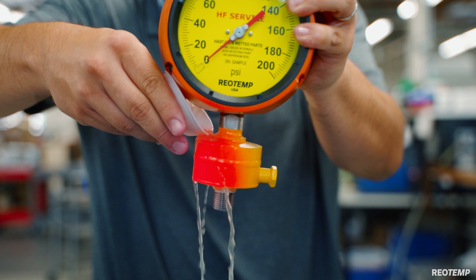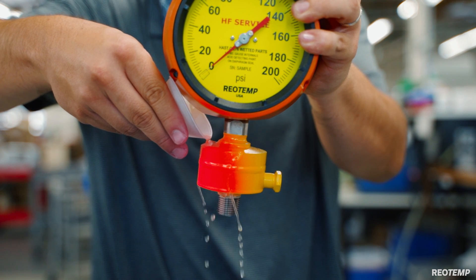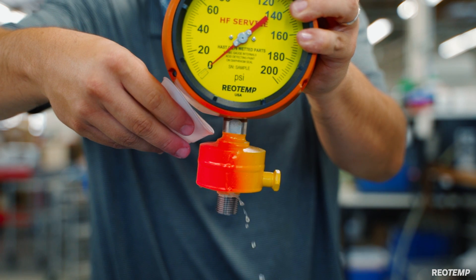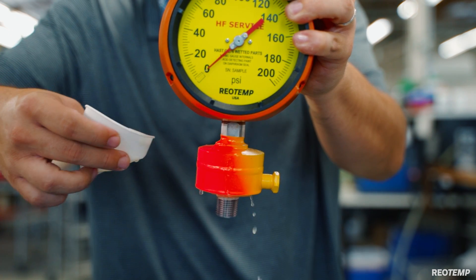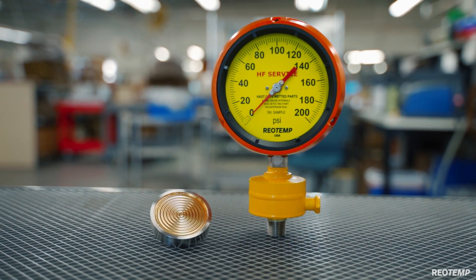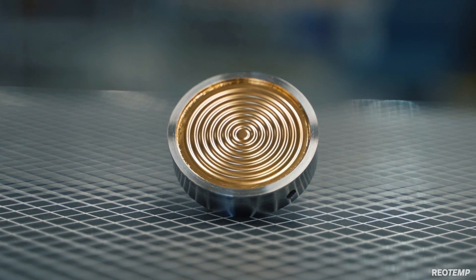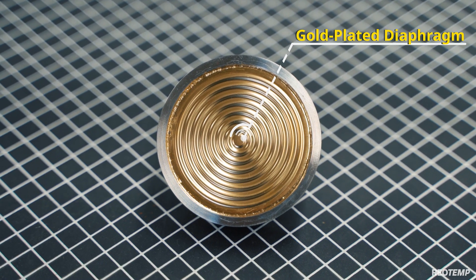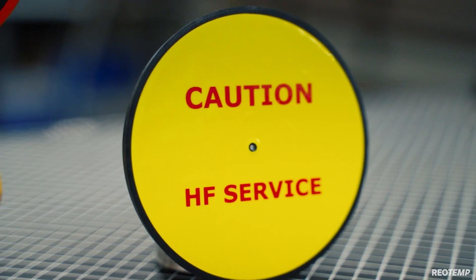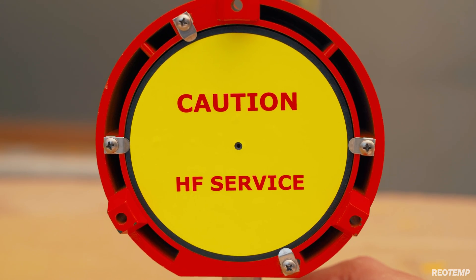This visual indication is imperative for operators to see that a leak has occurred so they can safely shut down the line and repair or clean as needed. For anhydrous HF service or in applications where hydrogen permeation is a concern, Reotemp offers an extra thick 24-karat gold plating on the backside of the diaphragm.